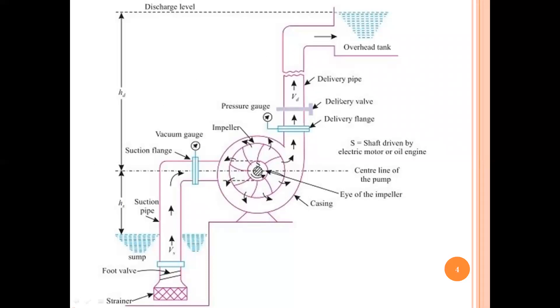This is the overall picture of your centrifugal pump. When drawing the centrifugal pump, the most important portion has the impeller. The central portion is called the eye of the impeller, then you have the impeller blades and casing. This pipe, which connects the bottom tank to your pump, is called your suction pipe. The distance from the center line of the pump to the water surface in the lower tank is called your suction head.